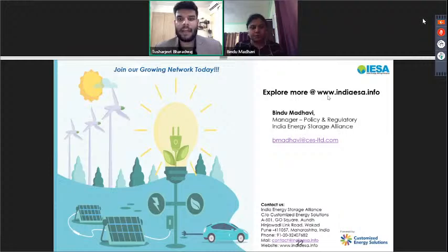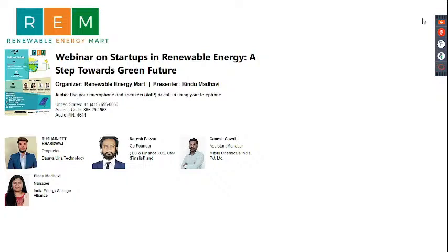The government is also helping you to get angel investors for your project. If you have any idea, you can get angel investors who are ready to fund your ideas. In the PV sector, yes, and even in the power sector also. Mandated standards are required, like IS 14286, which is equivalent to IEC 61215, and IS 61730 safety qualification. These two are currently mandated, and apart from that, PID is also mandated. So these three are the major standards required to avail any MNRE or government subsidies.